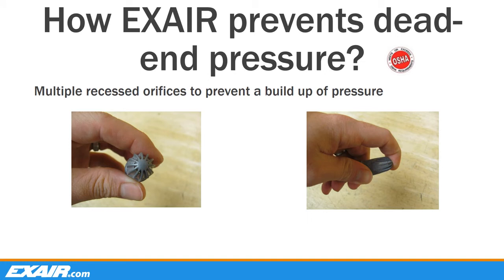Our Super Air Nozzles are designed to utilize multiple openings that are recessed behind a series of fins to prevent the nozzle from being dead-ended. With this design, the air always has a path to vent, so the nozzle produces air close to atmospheric pressure, well below OSHA's 30 psig dead-end pressure requirements.